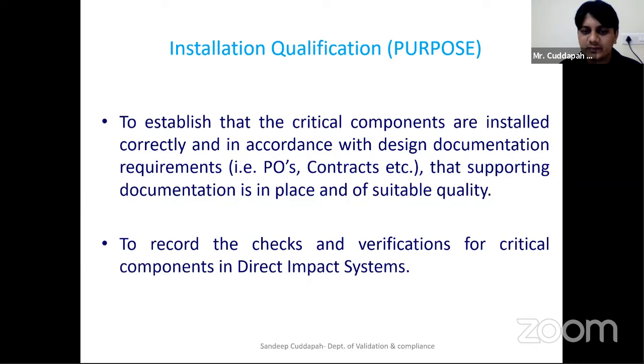If you have any small minor equipment which is connected to the direct impact system, suppose you have an autoclave, that is your direct impact system, because through that you take the sterile material. A small pressure gauge connected to the autoclave becomes an indirect impact system because it is connected to the direct impact system. That failure will not lead to failure of the autoclave, but it will have some consequences that will be listed out during risk assessment.